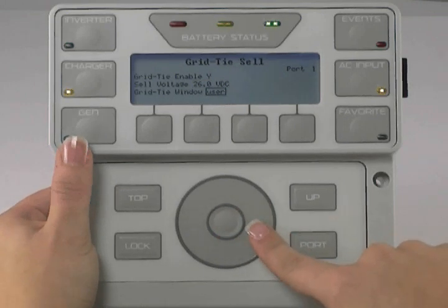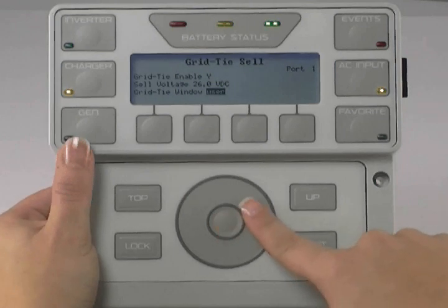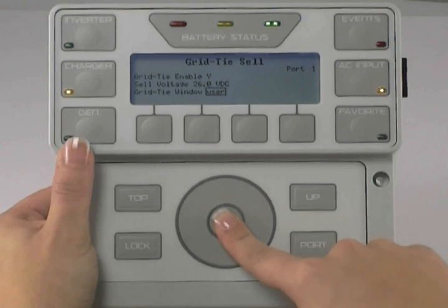Use the wheel to move to Grid-Tie Window. We recommend this be set to IEEE. If it is not set to IEEE, press the center button to highlight and use the wheel to adjust it. Press the center button to lock in your choice. Press top twice to get back to the main screen.